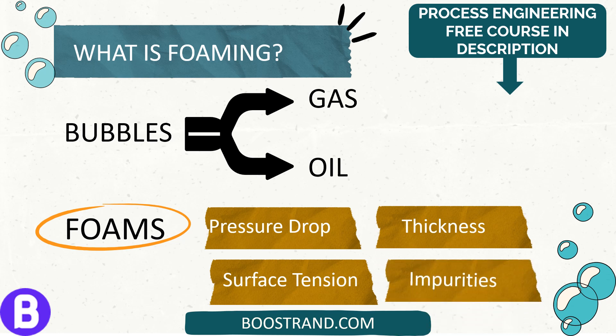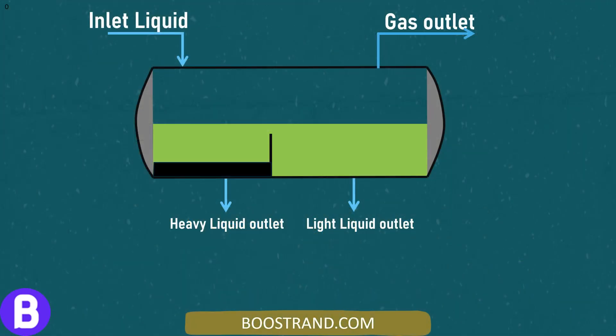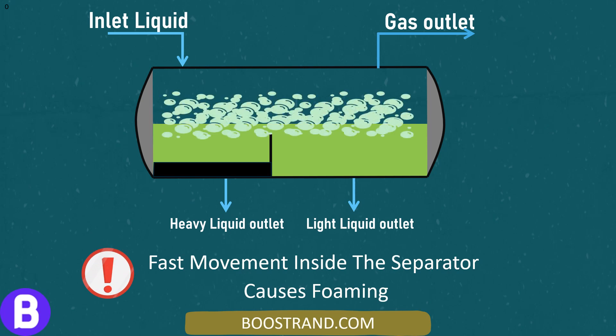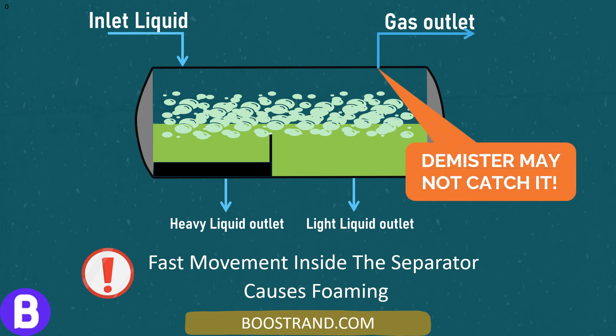When this happens, small droplets are formed and they get coated with oil. It occurs when the gas is released. Usually, fast movement inside the separator causes foaming. The foam covers the liquid's surface, making it tough for the gas to get out. Foam also takes up space in the separator for the gas and can get through the demister, escaping as a mix of mist and tiny liquid drops in the gas outlet.